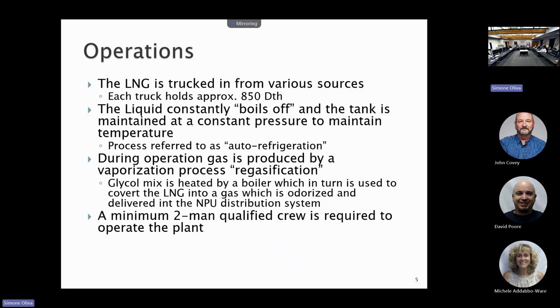If you've never seen the process, we have a picture of a blow-off later, when we remove the remaining pressure off of that tanker truck before it goes back on the road. It's a very volatile and dangerous process, right? You're using a cryogenic pump to move negative 260 degree liquefied natural gas from a tank to a larger holding facility, with stainless steel hoses and all the safety gear that goes along with that. It's a very impressive process to watch. I'm going to throw the word potentially in there. We're using volatile gas. There are very strict processes and procedures that we follow to ensure the utmost safety. Very, very specific, step-by-step process.